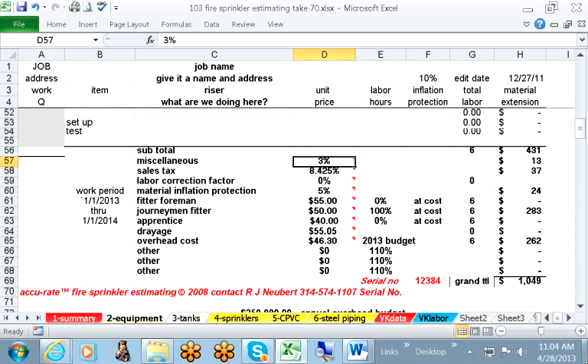Below the line, you have a miscellaneous. 3% is referenced to tape, putty, pipe dope, cutting oil, whatever you might consider as miscellaneous. That's not included in your estimate or your overhead. Change it to 5%, whatever. 8.425 represents the state of Missouri sales tax and including the local sales tax. If it's a tax-free job, you put a zero in it.